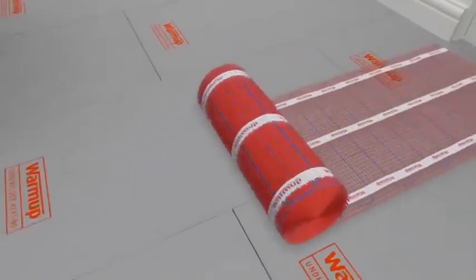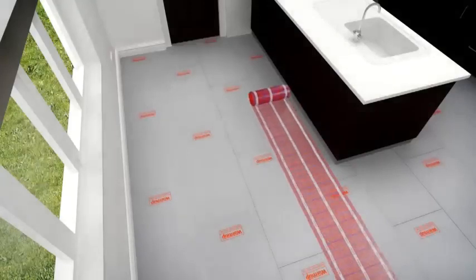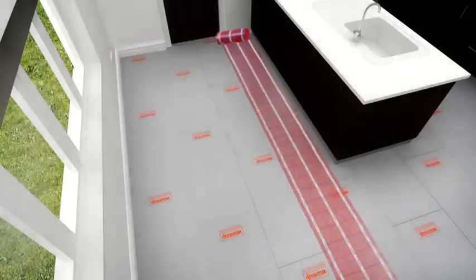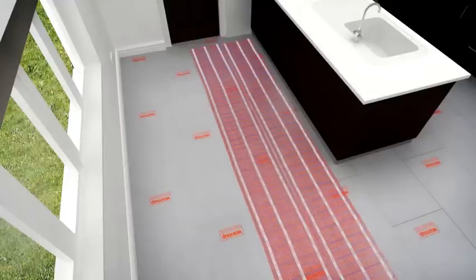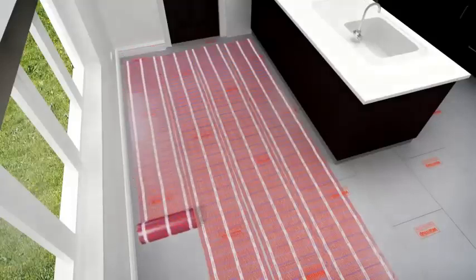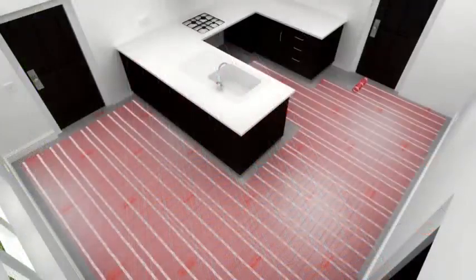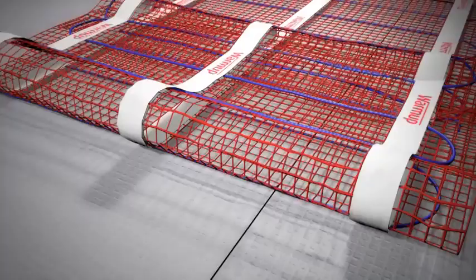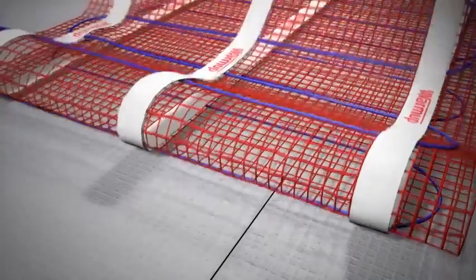The matting system can be cut and turned and modified to fit a specific area. Never cut the heating wire and be careful not to damage the heating cable. Affix the matting to the subfloor using the double-sided tape on the mat.